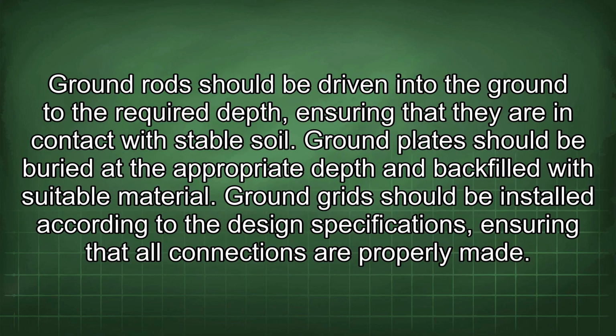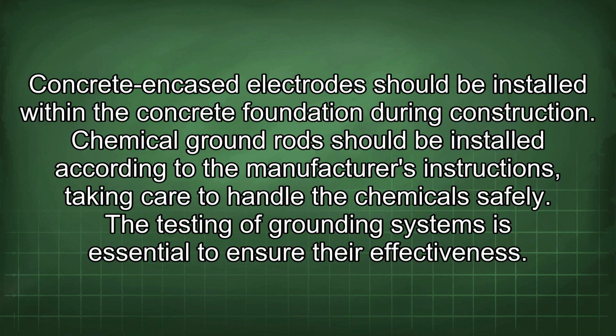Ground rods should be driven into the ground to the required depth, ensuring that they are in contact with stable soil. Ground plates should be buried at the appropriate depth and backfilled with suitable material. Ground grids should be installed according to the design specifications, ensuring that all connections are properly made. Concrete encased electrodes should be installed within the concrete foundation during construction. Chemical ground rods should be installed according to the manufacturer's instructions, taking care to handle the chemical safely. The testing of grounding systems is essential to ensure their effectiveness.